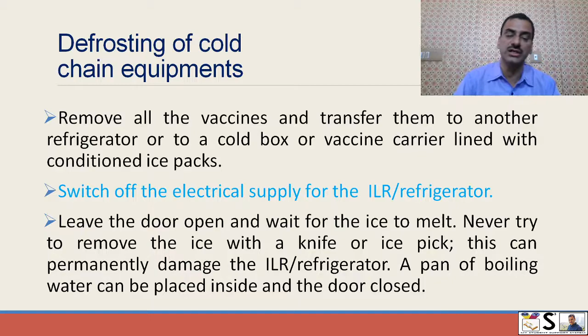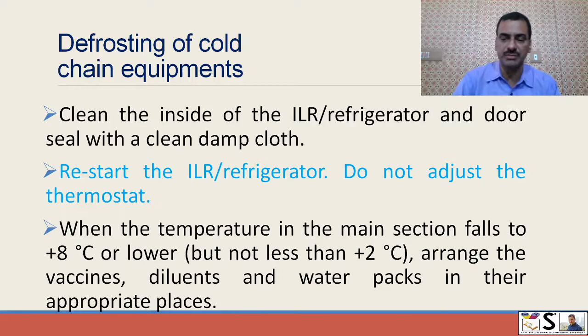Clean the inside of the ILR or refrigerator and the door seal with a clean damp cloth. After cleaning and drying, restart the ILR. Do not adjust the thermostat. When the temperature in the main section falls to 8 degrees or lower but not less than 2 degrees, arrange the vaccines or diluents and water packs in their appropriate place.